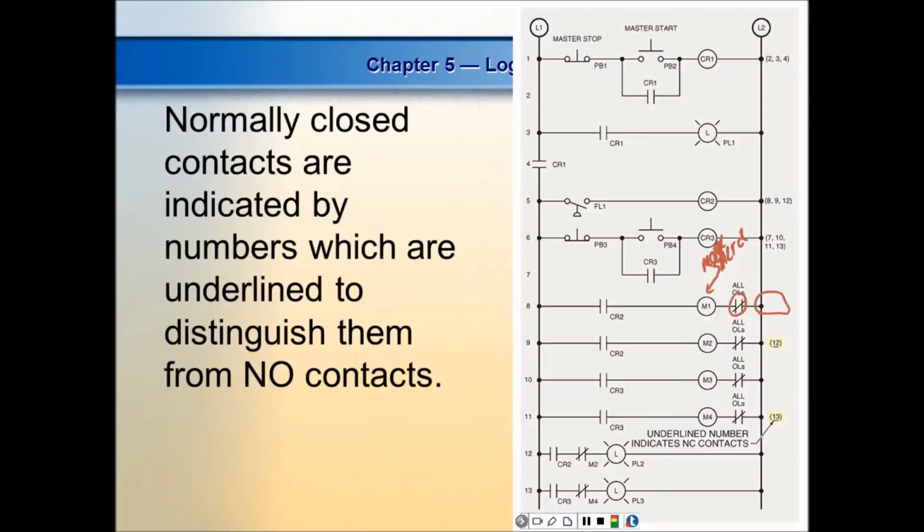This is the control diagram. That's exactly right. Somewhere I'm going to have a diagram that has my motor, if it's a 3-phase motor, and this is going to be labeled M1, M2, and M1, M1, M1. So this is not the power circuit, this is the control. That guy has no auxiliary contacts on it. So if it does not have a contact within the control circuit, there's not going to be any numbers out there. But it will have contacts within the power diagram, right?